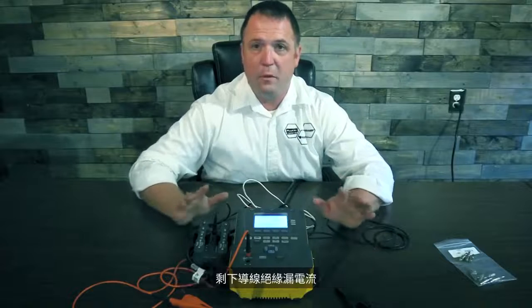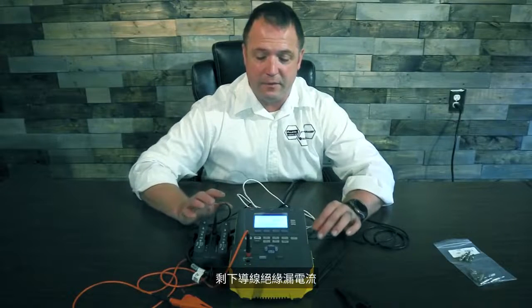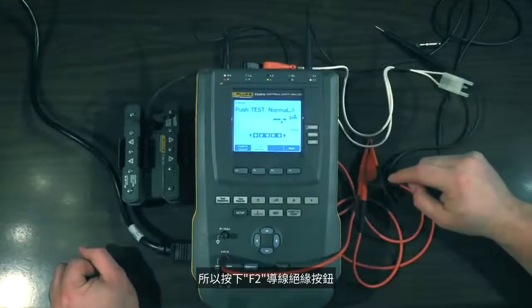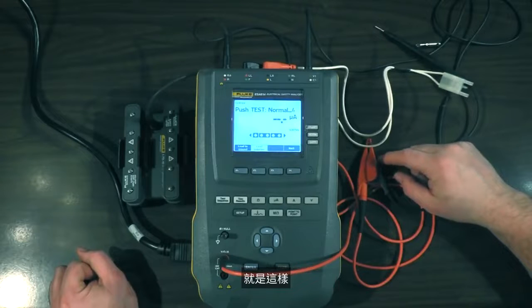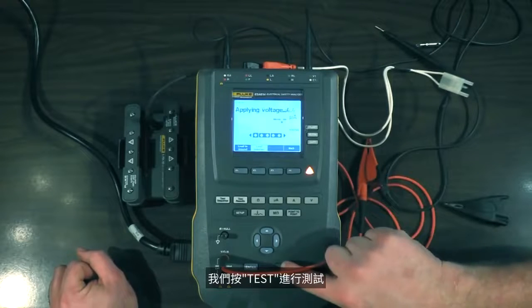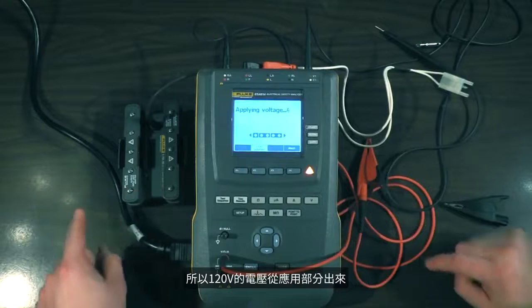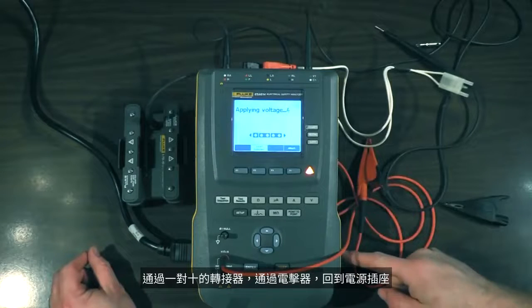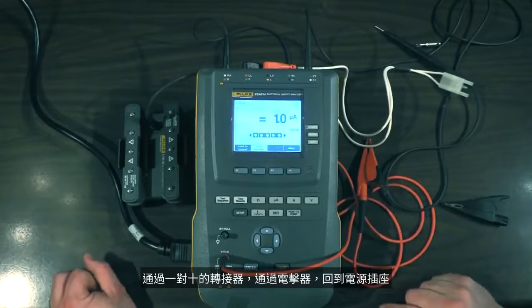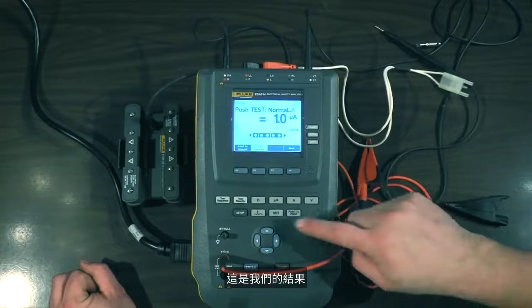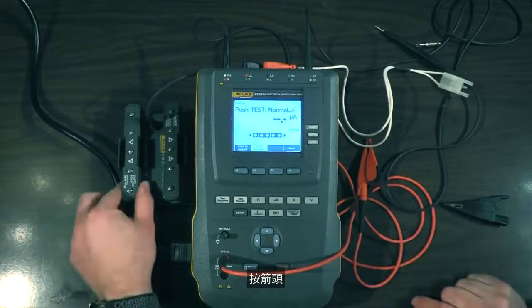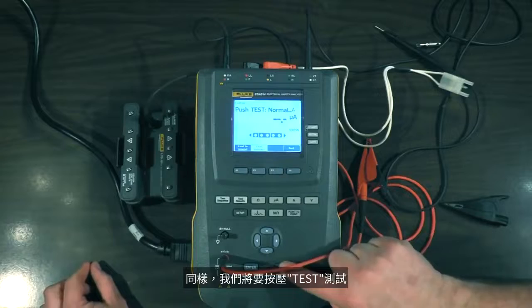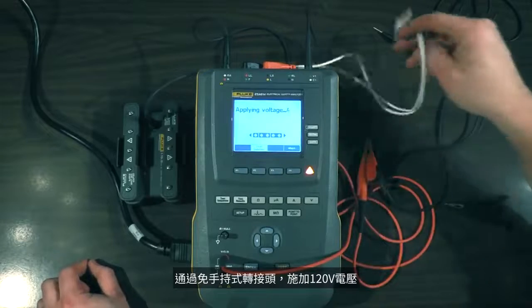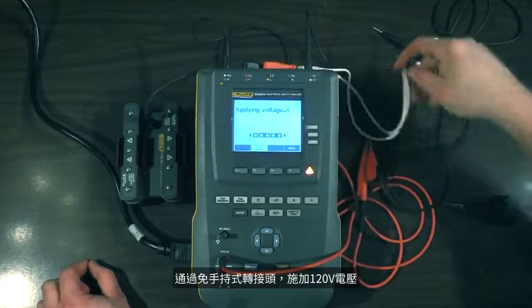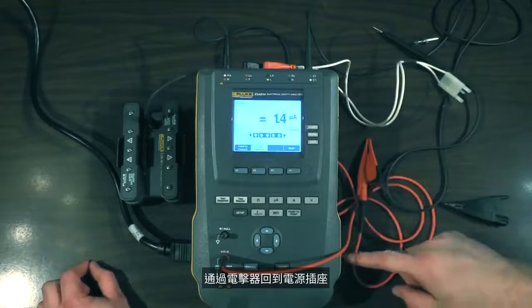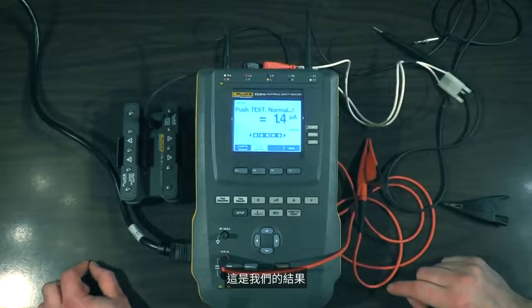There we go. What's left is the lead isolation. So push the lead isolation button. There we go. And we're going to push test. So 120 volts comes out of the applied parts through the 1 to 10 adapter, through the defibrillator, back into the power port. There's our result. Over arrow. Again, we're going to press test. 120 volts through the hands-free adapter, through the defibrillator, back through the port. There's our result. There we go.